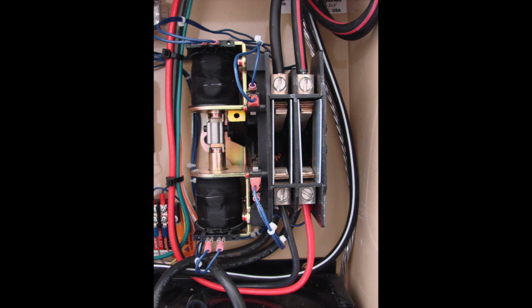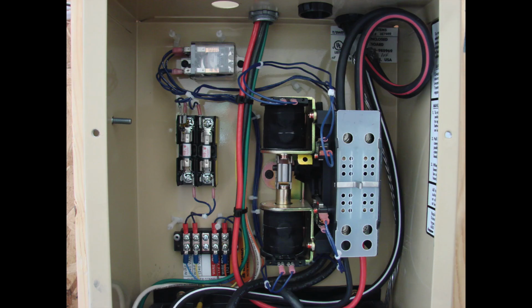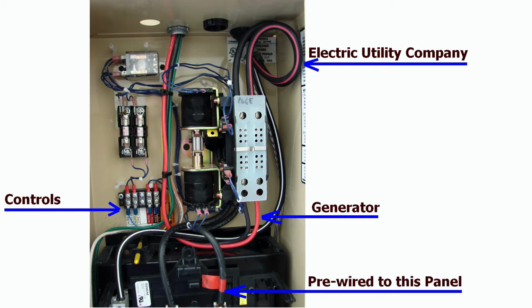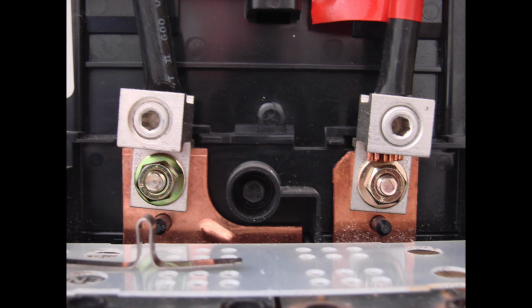And we also see where from this transfer switch contact mechanism, there are a pair of wires that actually go down and feed this enclosed subpanel that is part of this assembly. So we don't really have to do anything with that. You can check those if you want to for the tightness of those lugs to make sure everything is nice and tight.